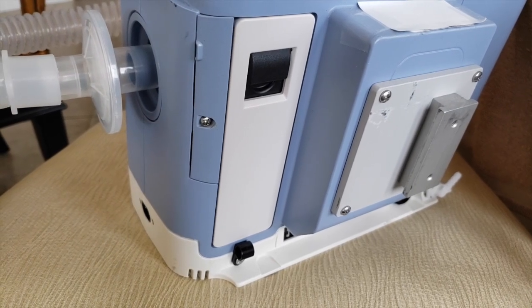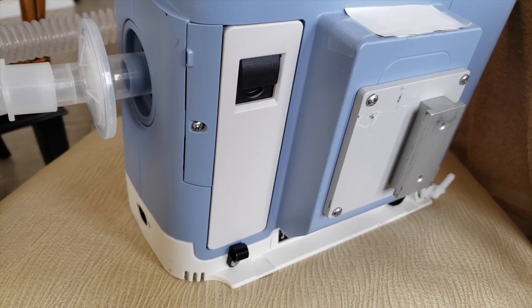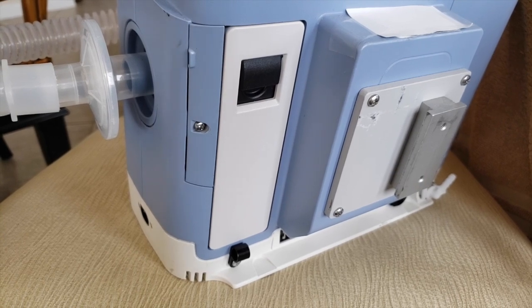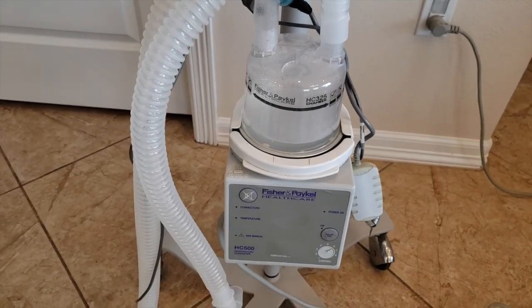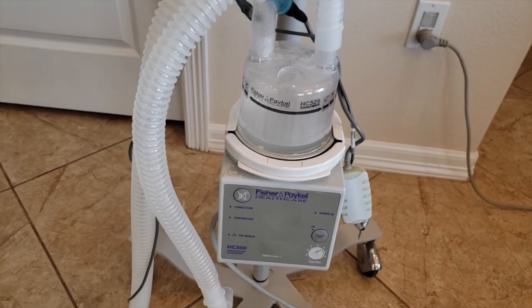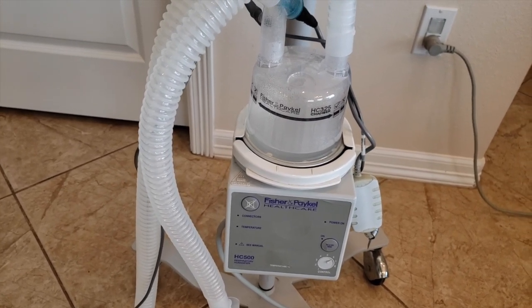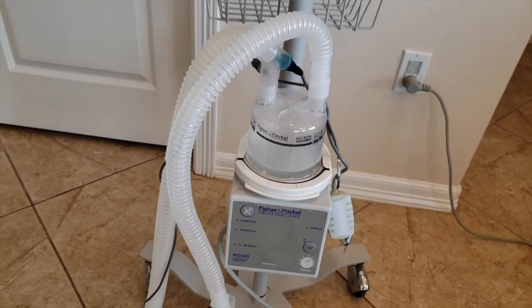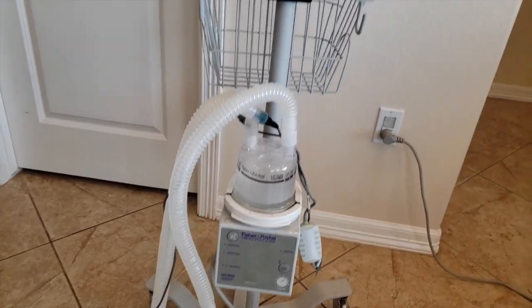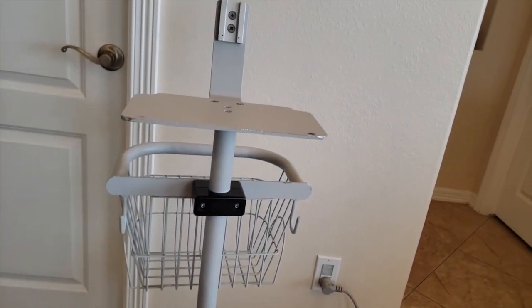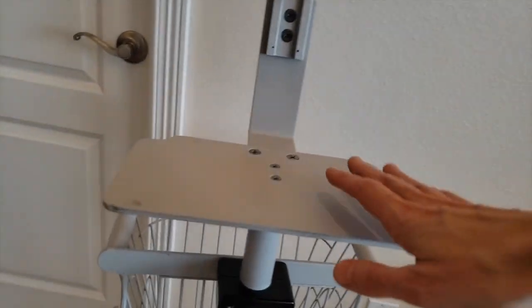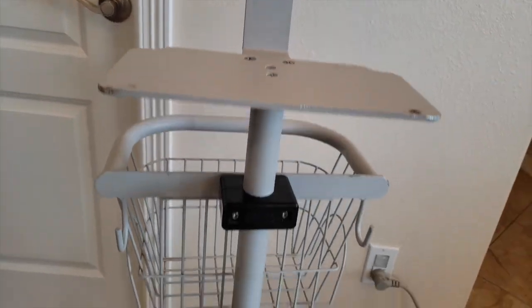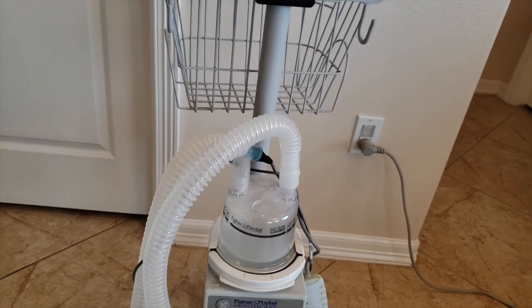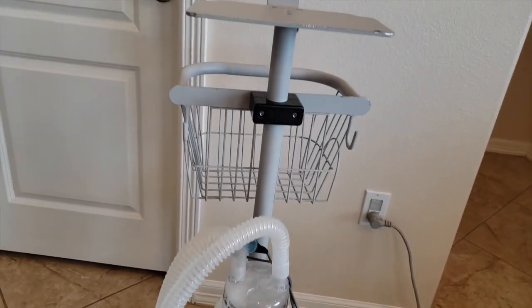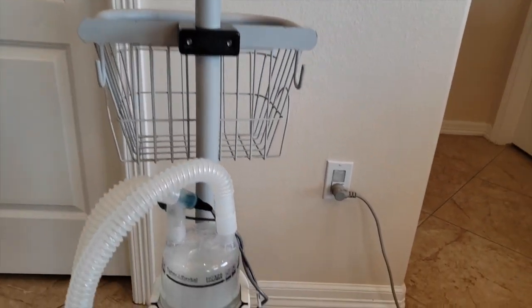Let me show you how this gets connected up to a machine called a heated humidifier. This machine down here is called a heated humidifier. The best way to connect it to a ventilator is using this contraption. It is called a ventilator stand or a ventilator cart. The ventilator will sit right up here and then you can loop down the connections down to the water chamber. This makes everything stay upright. So let me show you how you do that.